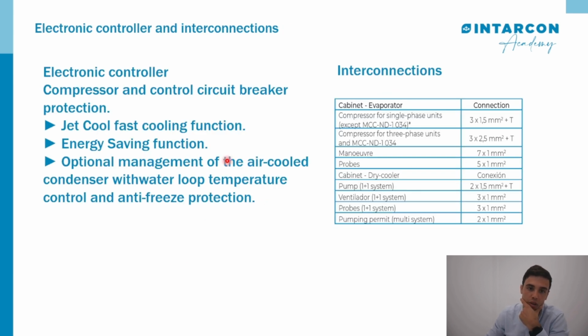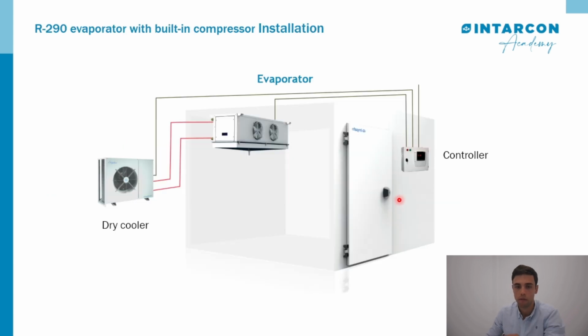So the electronic controller will have three main functions: jet cool fast cooling function, energy saving function, or optionally managing the air cooled condenser, for the water loop temperature control and antifreeze protection. In the part of interconnection that we saw before, let's see the different connections that you will have depending on the function of maneuver, probes, pumps, fans, pumping permits also for this equipment.